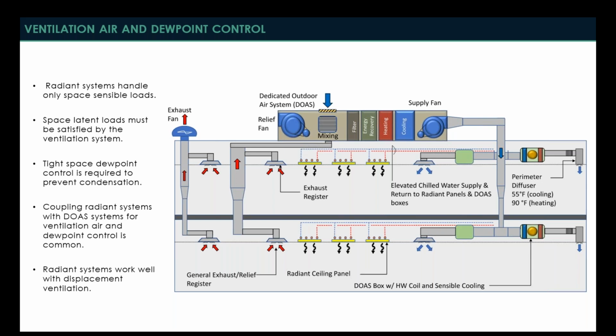If it is doing latent cooling, that means it's going to have condensation on it, and that's a very bad thing. So that's why the tight space dew point control from the DOAS system is so critical, because we want to avoid having condensation. And what that means is the DOAS system is going to maintain a dew point temperature in the space that's 2 to 3 degrees below the surface temperature of the radiant system to make sure that there is no condensation.